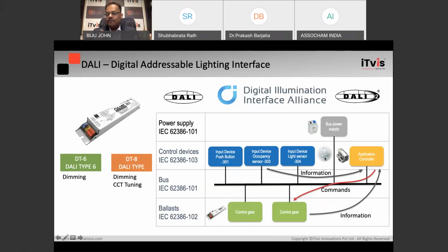There is a difference between DALI broadcast and DALI addressing. DALI broadcast is one-way communication, and DALI addressable is two-way communication. This is also covered in the DALI 2 standard. Gone are the days when people used to fight each other: my control gear is good, your controller is not good; my controller is good, your control gear is not good. That compatibility issue is no longer there in lighting management systems after DALI 2 came into the picture, because even the application controller is tested.